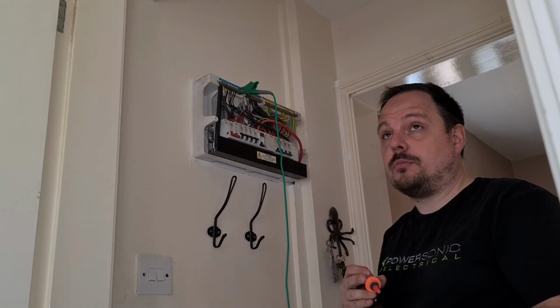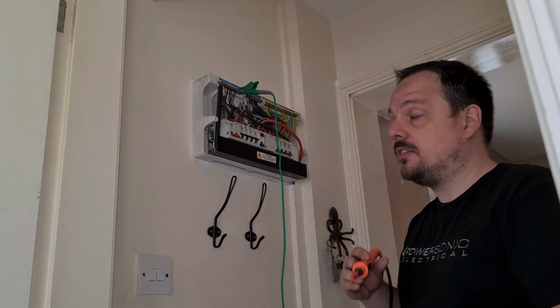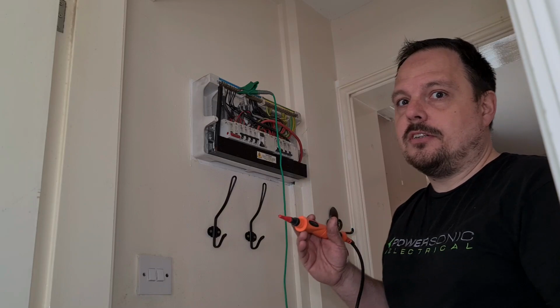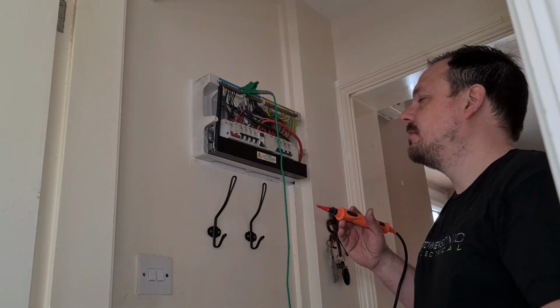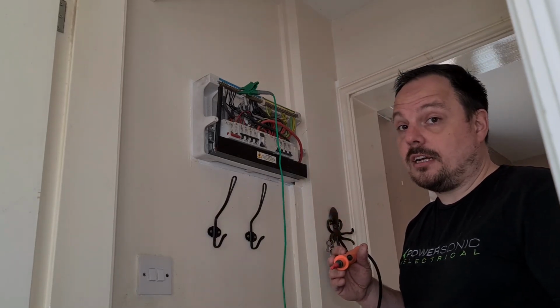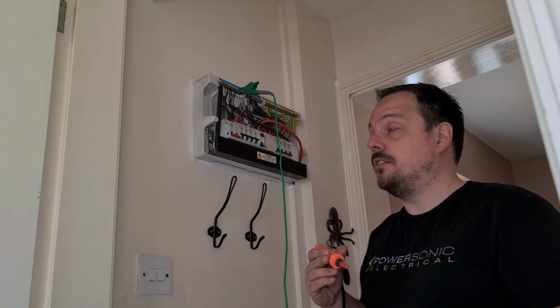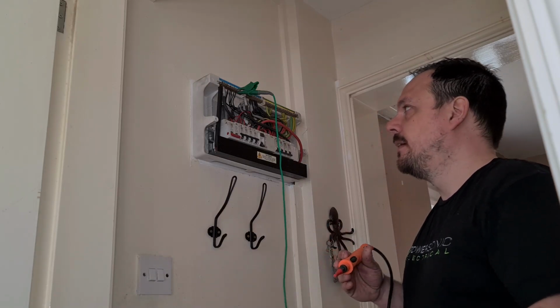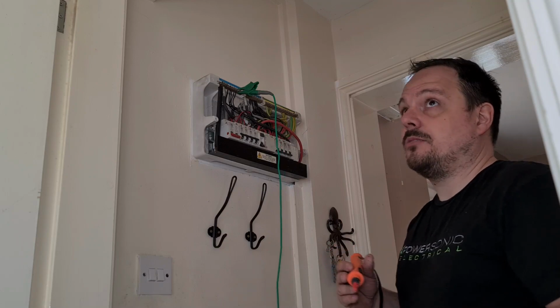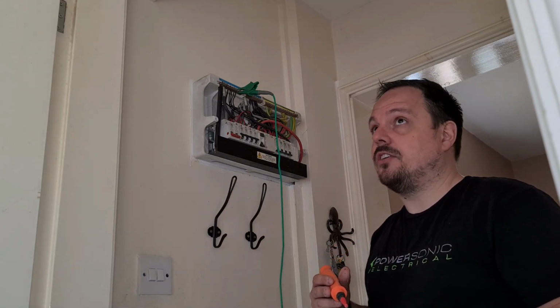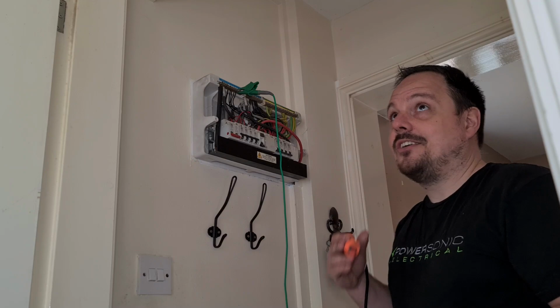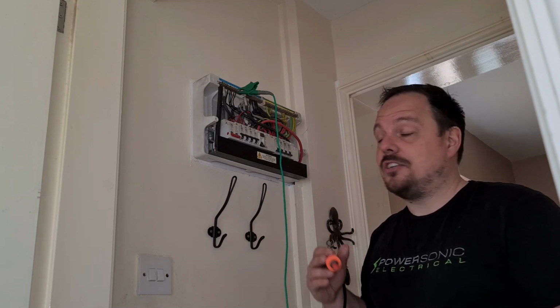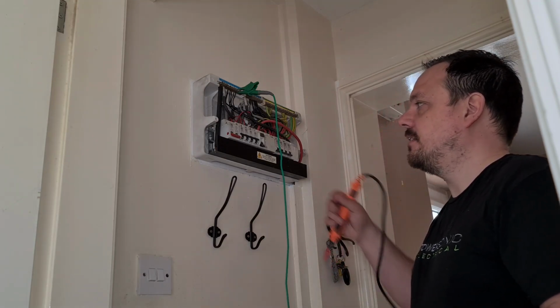And if you want to go to the trouble of disconnecting all of the light fittings, the immersion elements that might be on there or whatever else, then you can do. If you've got local isolators, it makes it a little bit easier, so you can just test up to that point of isolation for the connected equipment. But let's be honest, if you've got a house full of spotlights, you're going to cause more damage and destruction going around doing that, interfering with the installation, than adjusting the way you carry out your testing.